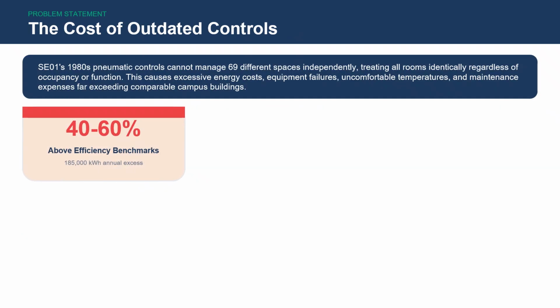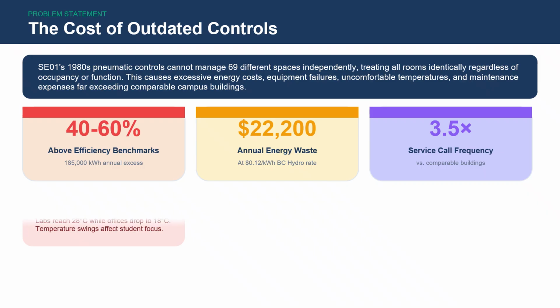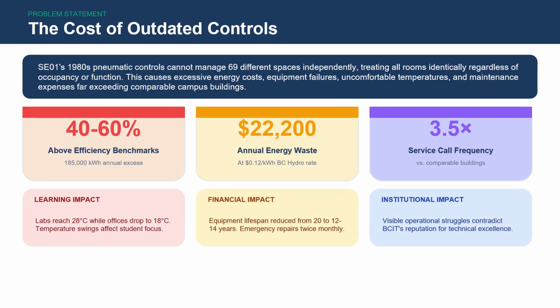The problem tells the story. 185,000 kilowatt hours of excess consumption annually. At BC Hydro's rate of 12 cents per kilowatt hour, that translates to $22,200 in wasted energy costs every year. However, beyond energy, service calls occur at 3.5 times the rate of comparable buildings. Labs reach 28 degrees while offices drop to 18. Equipment that should last 20 years fell in 12 to 14. And perhaps most importantly, these visible operational struggles contradict BCIT's reputation as an institution of technical excellence.